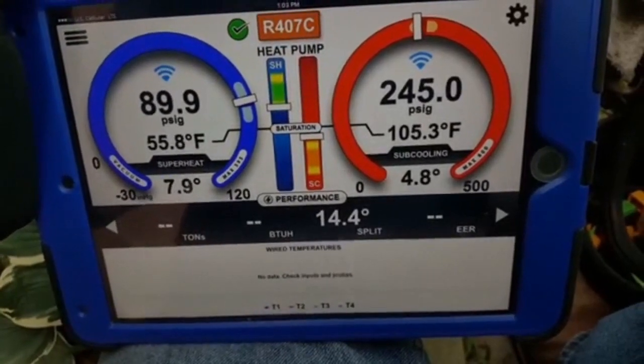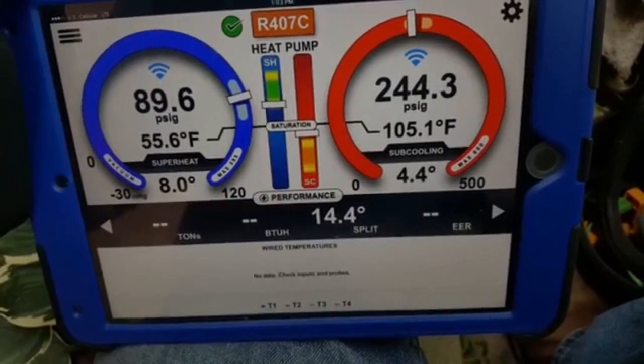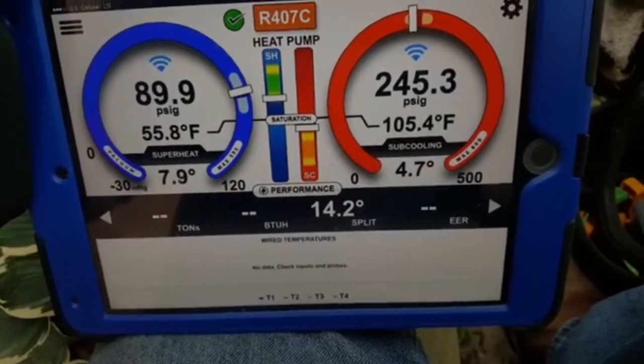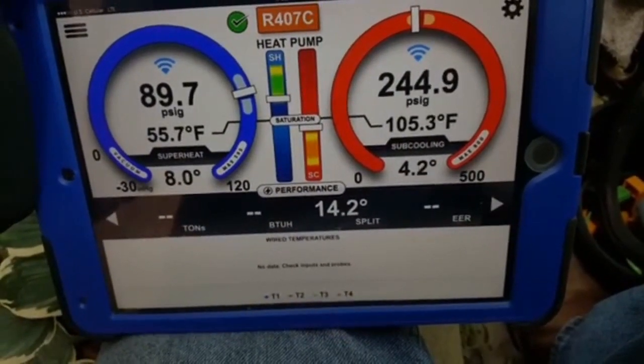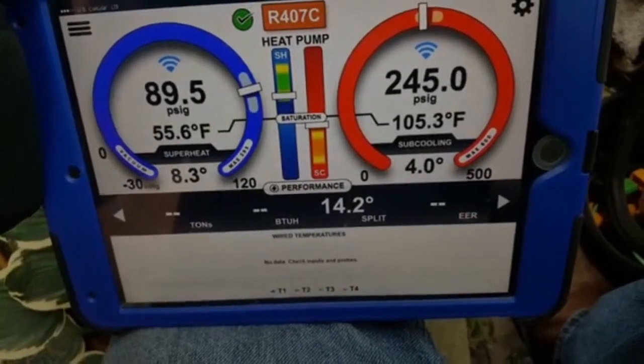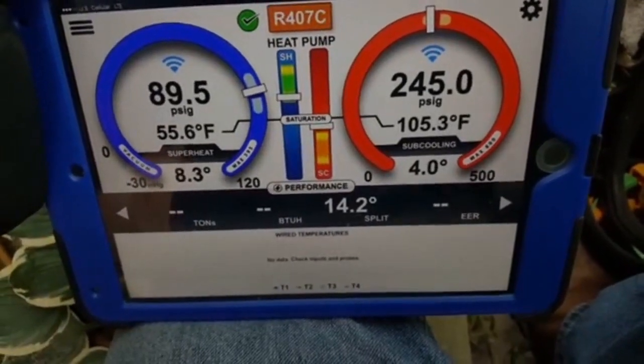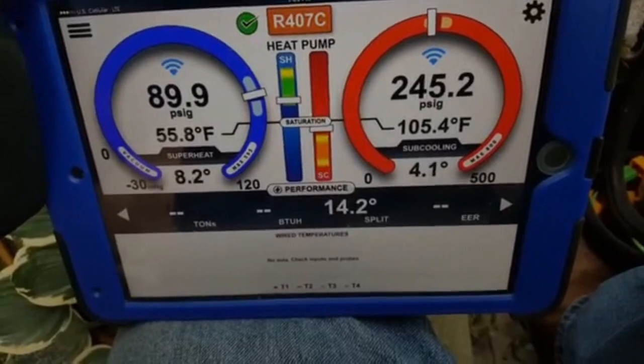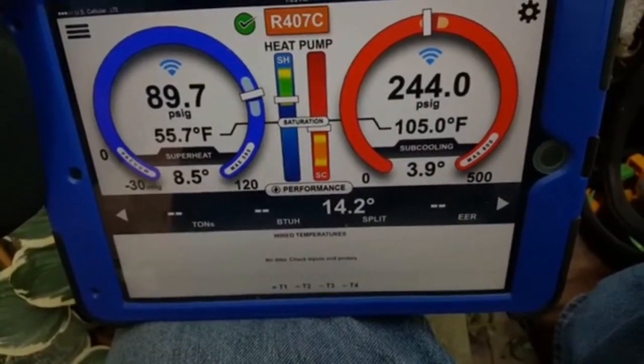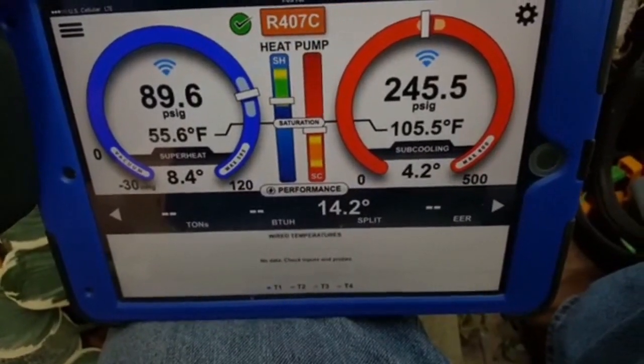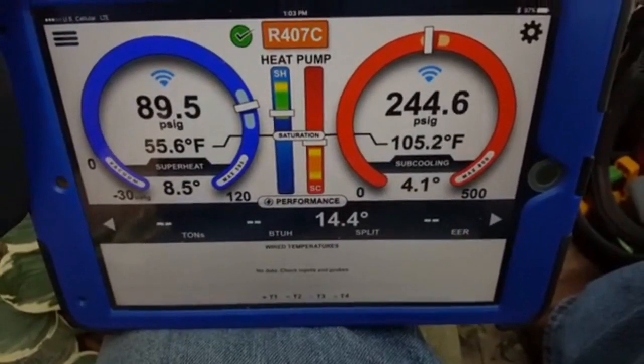I don't know if I'll change that charge at all, because really, we've got a mismatched system. We're not quite to the factory charge, but on a lot of mismatches that's what happens. There is a TXV, but as this thing runs, I bet that subcooling comes up a little more once it gets cooler inside. But we'll see, we'll let it run for a while.